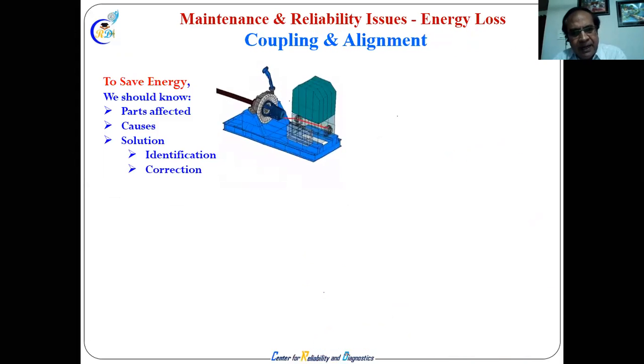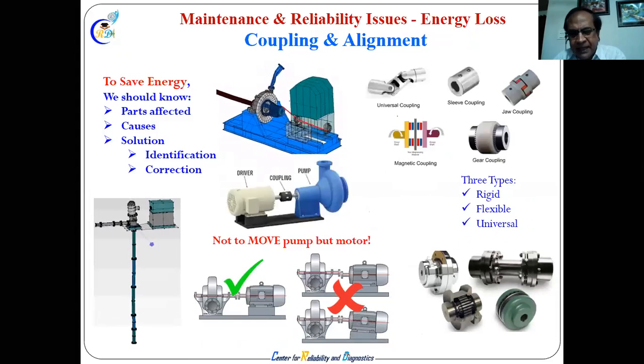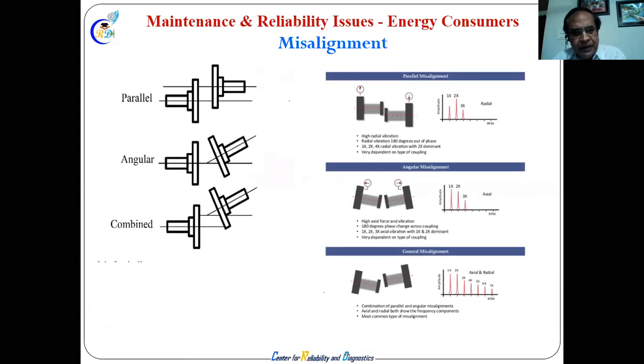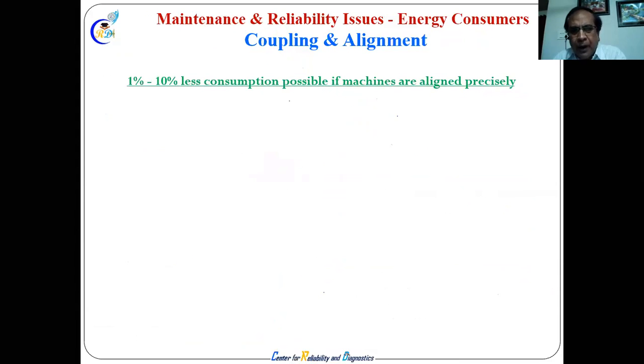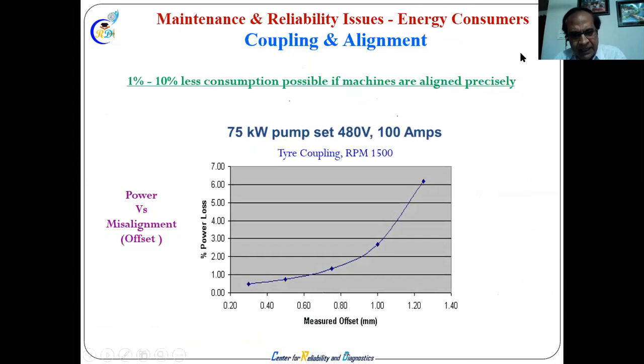Then coupling alignment. Every alignment has a problem, and alignment has energy saving. There are different types of misalignment, and we get 1 to 10% less consumption if properly aligned. There are studies available. If there is a 1 mm offset of a machine, offset meaning parallel misalignment, then you get this much power loss. So there are cases available on different alignment, 0.01, 0.02 mm, depending on the machine.